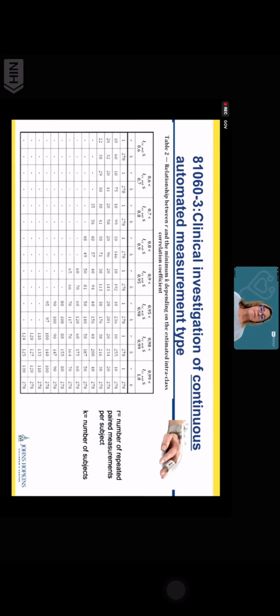And actually, let's just go past that one and the next one, and we'll go for time. One more. After that. No, keep going. Yes. So the one thing I did want to highlight for the continuous blood pressure devices is that the standard requires that the paired values be less than or equal to 6 millimeters of mercury with a standard deviation of less than or equal to 10 millimeters mercury. Next slide. Which is very different than what is required for the cuff devices, where you can see what the performance standards are here. Next slide.